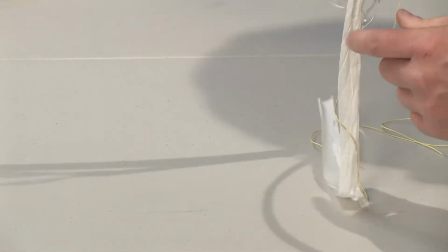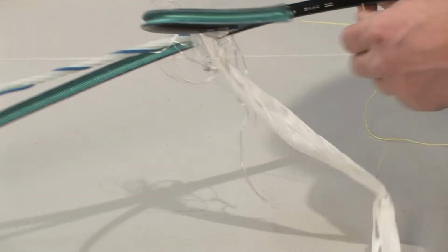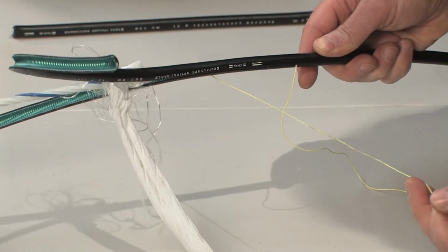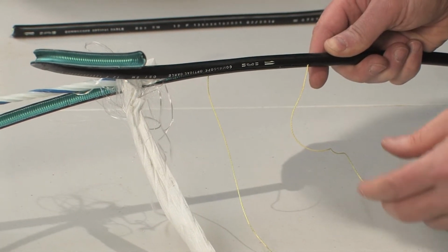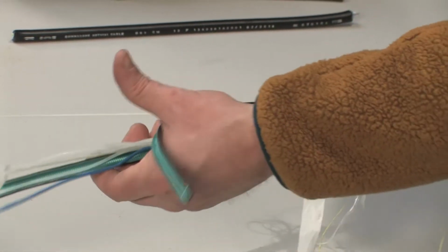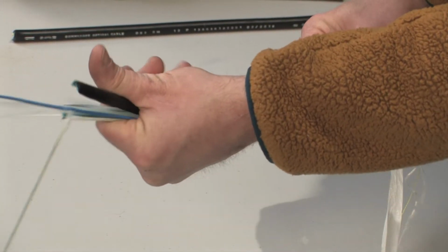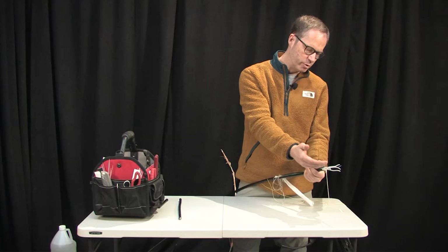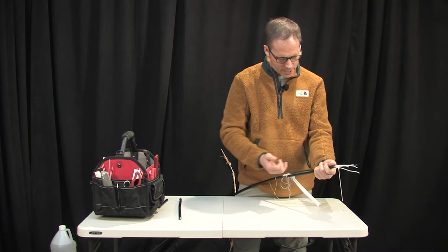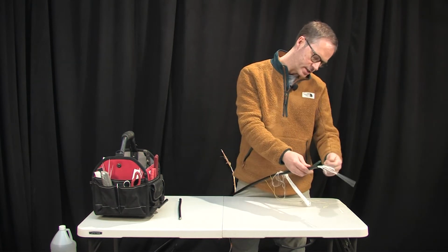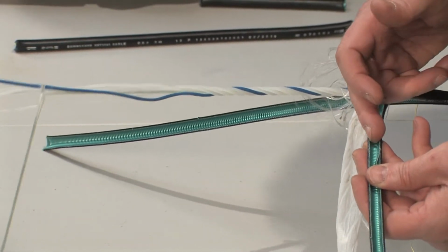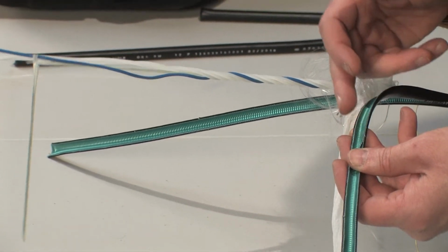giving you access to be able to work on a single buffer tube within that. One thing that I overlooked in our conversation here was these rip cords. We don't always have a rip cord within the fiber cables themselves. Nowadays, generally there'll be 2, and the purpose of that is to be able to create what you see here. We would expose the end of this fiber, we would have these 2 rip cords inside the cable, and then you would start the rip cord on one side, ripping it down, start the rip cord on the opposite side, rip it down, and then that opens the cable up for us to be able to work on it instead of having to try to manually take this apart.